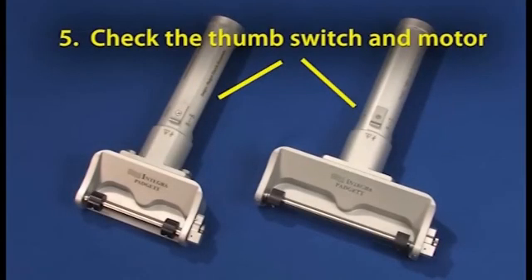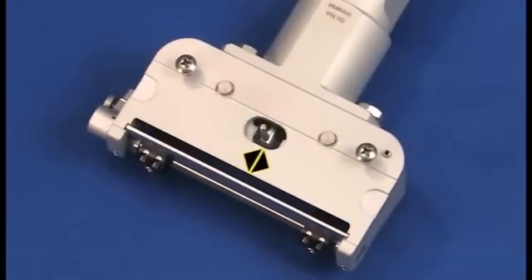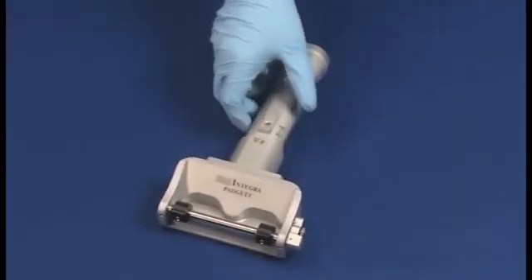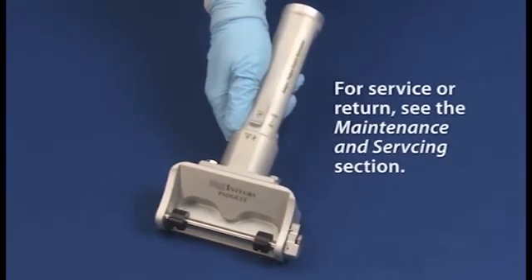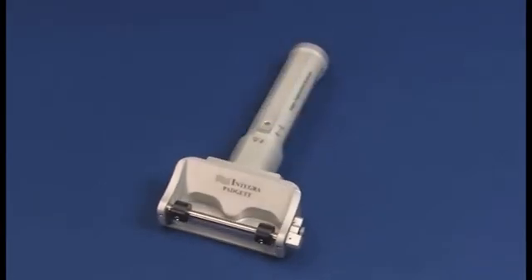5. Depress the thumb switch on the dermatome handpiece momentarily. The dermatome motor is to run, and the oscillating pin is to move rapidly from side to side. Note any unusual motor sounds. If issues are experienced with any of these system checks, do not use the dermatome, and return the unit to the Integra Padgett Dermatome Service Center for service. If no issues are observed during this assessment but performance issues are experienced, refer to the following troubleshooting table.